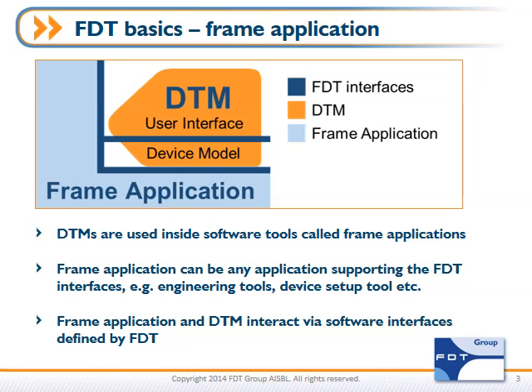The second part of the FDT standard is called the frame, or frame application. DTMs are used inside of a frame application to communicate with all the individual devices in the factory automation architecture. The frame application itself can be any type of application that supports the FDT interfaces, such as PLC engineering tools, basic device setup tools, HMI, and other types of applications. The frame application and the DTMs within it interact on software interfaces that are well defined in the FDT standard.